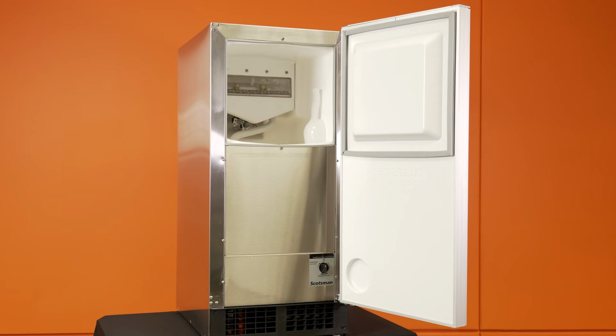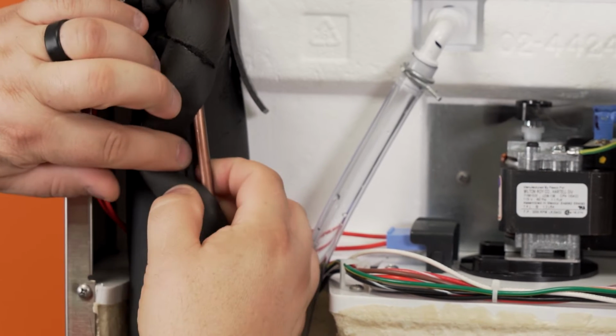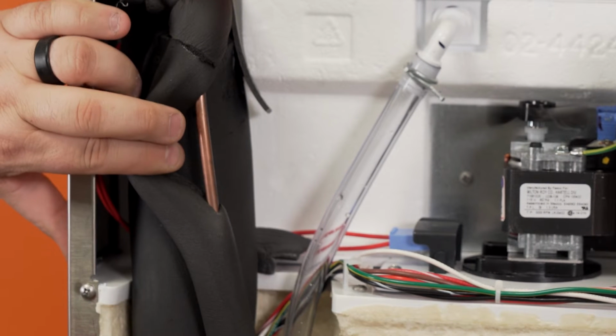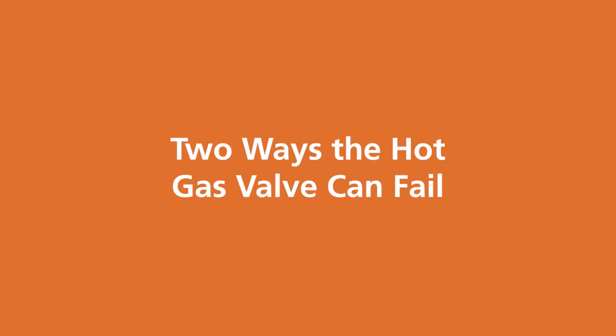A failure of the hot gas valve is one of several reasons a Scotsman residential ice machine may be experiencing slow or no ice production. The hot gas valve provides hot gas to the evaporator in order to harvest the ice from the evaporator. There are two ways that the hot gas valve can fail.